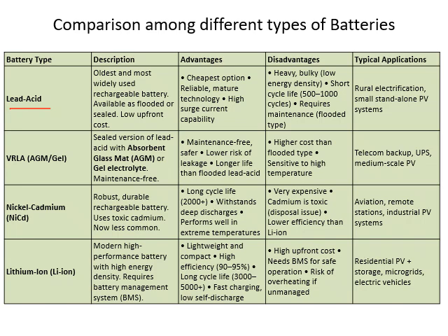And then if you are talking about the telecom backup, where you must have continuous flow of electricity, UPS, then medium scale photovoltaic, going for the gel batteries is one good choice. So AGM means absorbent glass mat or gel electrolyte. So it's maintenance free, right? So it's a good one to set up for the telecom, because telecoms are usually set up on high hills or areas where people do not reside. So there's nobody to go and check every now and then for the quality. So you should pick the maintenance free type, although it's a bit more costly, right?